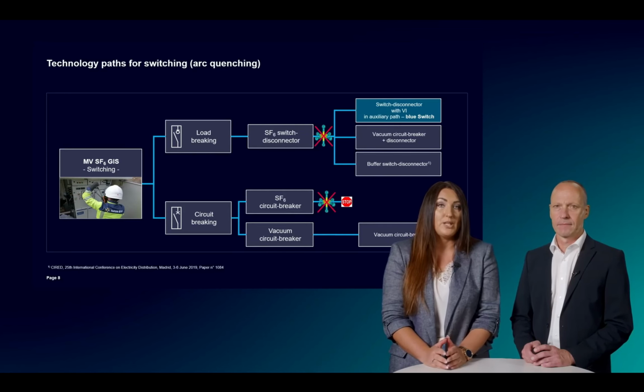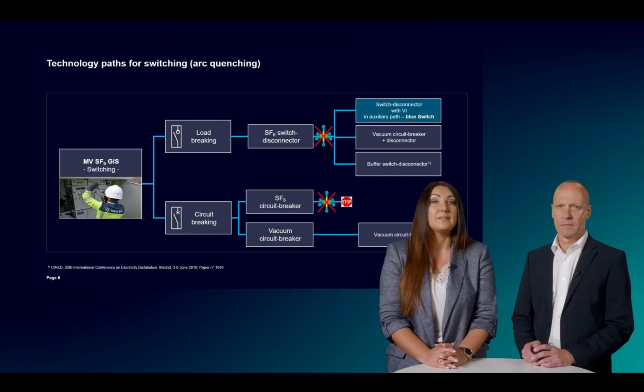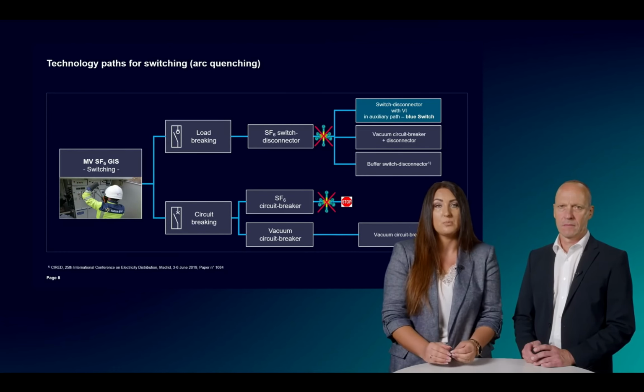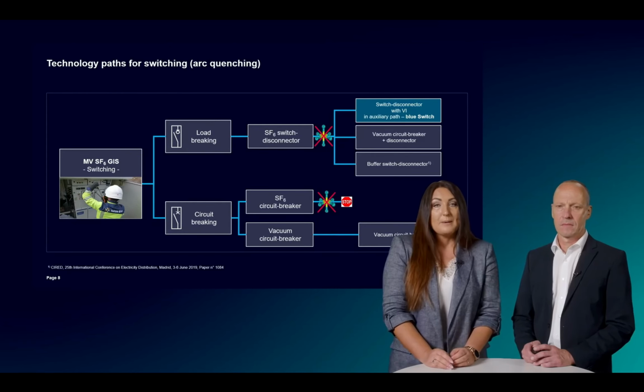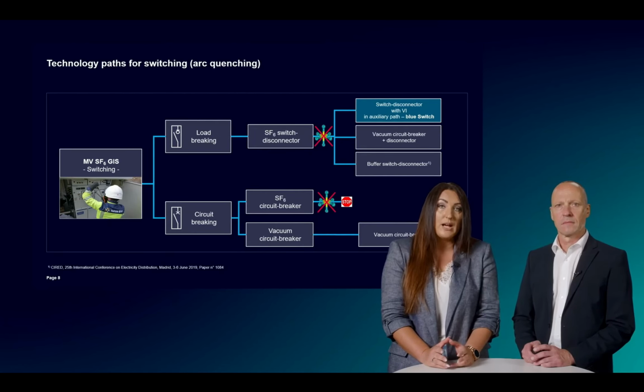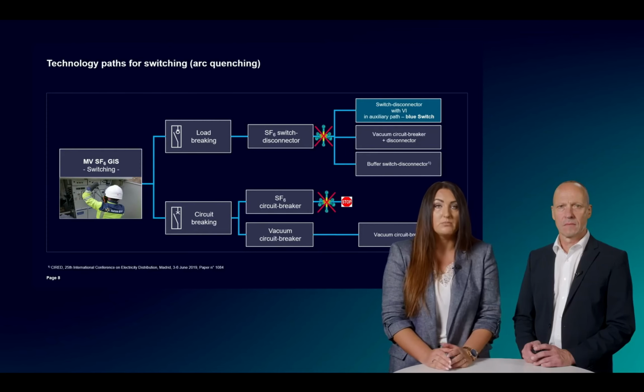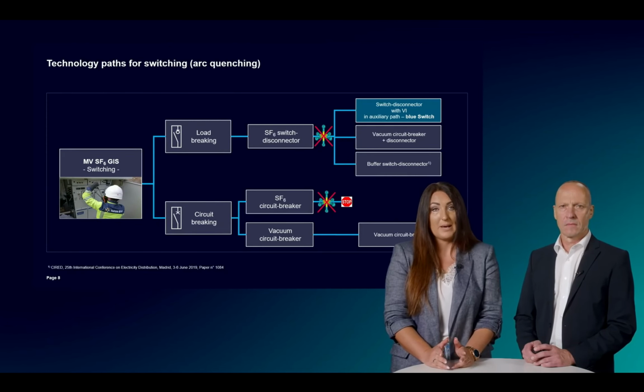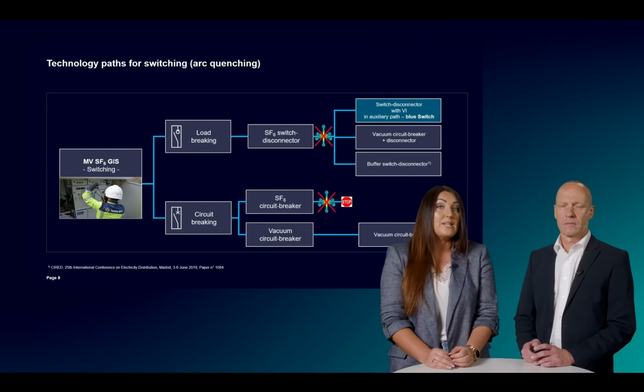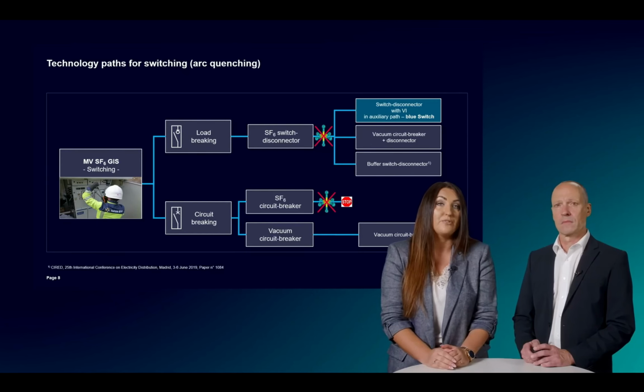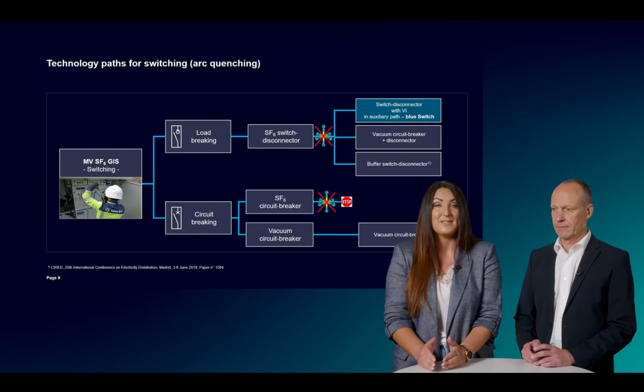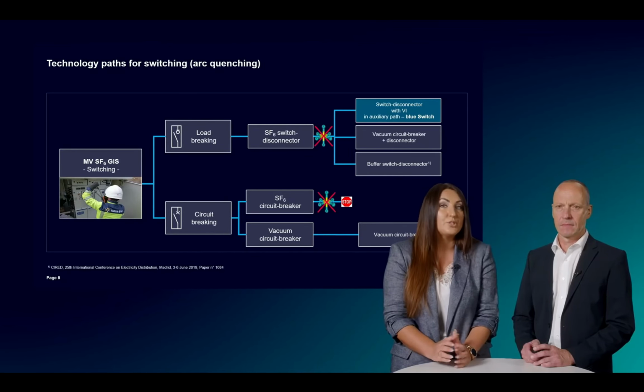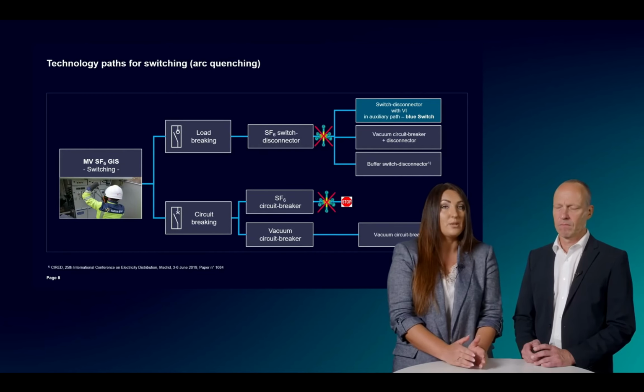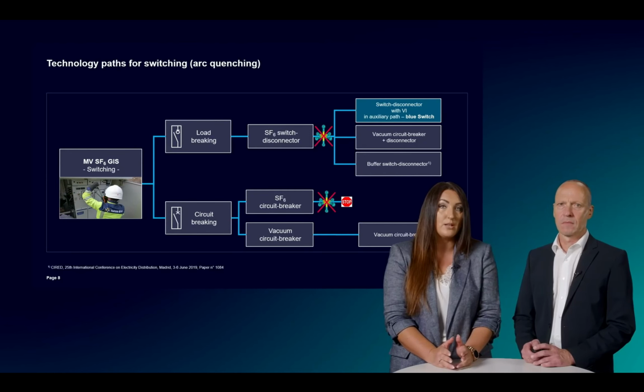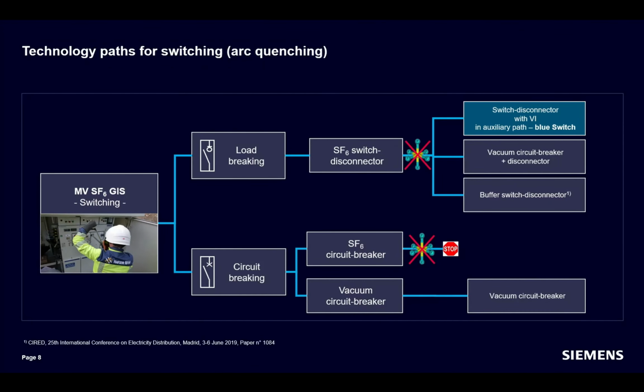Then another possible approach for load break switching is a so-called buffer switch disconnector. In this design, the filling gas does not only act as an insulating medium, but is also responsible for extinguishing the switching arc. A wide range of properties have to be taken into account, including arc extinguishing behavior, the electric performance, regeneration capacity, and last but not least, deposits and gas contamination after arcing. And as there is no long life experience for the buffer switch technology in combination with the natural origin gases, Siemens decided to go for an alternative with the well-proven, known vacuum technology, using a vacuum interrupter for arc quenching, but now in the auxiliary path, the so-called blue switch.